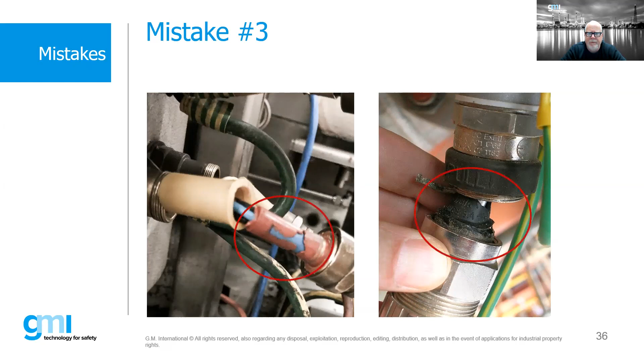And then what we see on the right-hand side, we see packing of the glands after the fact by taking some compound. So again, I'm highlighting a lot of things with cable glands that have to do with installations. But again, we want to be aware because these faults can occur at all different kinds of areas. These are just two examples of glands that, again, are not properly installed. On the left-hand side, that's a barrier gland going into a flame-proof box that wasn't properly poured or packed, if you will. On the right-hand side, that happens to be an example of a diaphragm seal that was torn, that, again, the installer should have caught that before it was installed, and check it out. Make sure that those issues are not there.